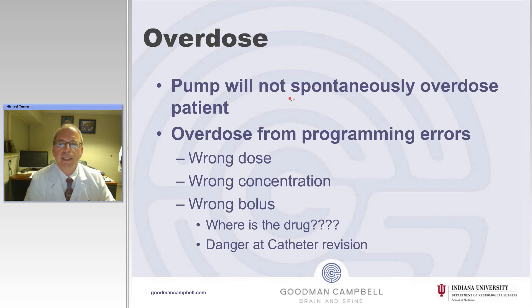However, humans program the pump. So the wrong dose can be entered, the wrong drug concentration can be entered, and the wrong bolus.